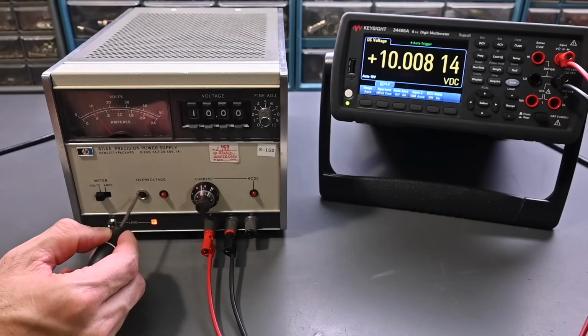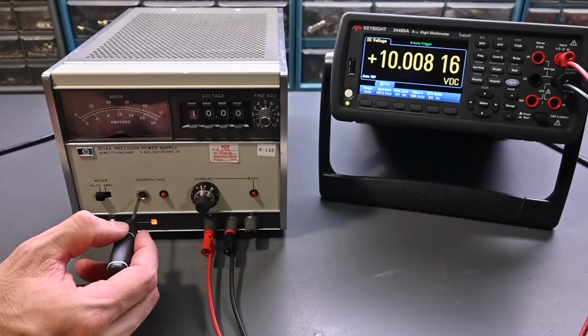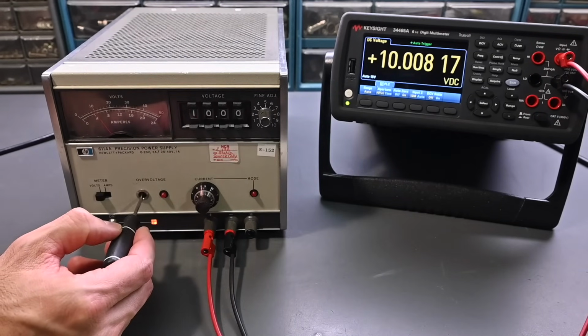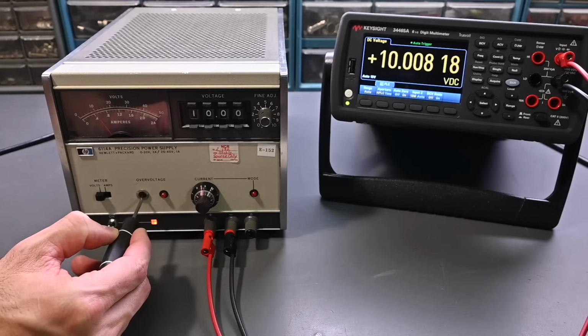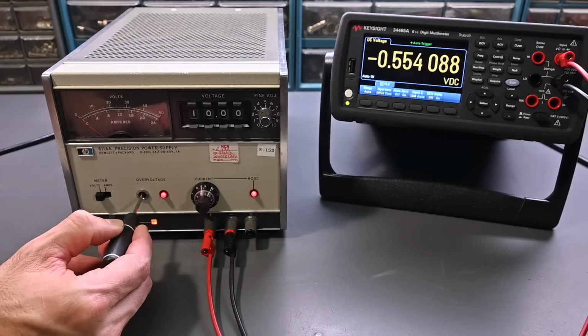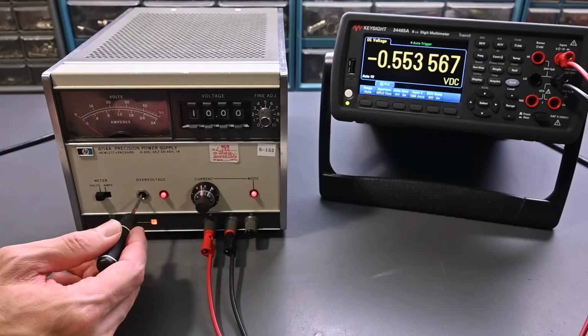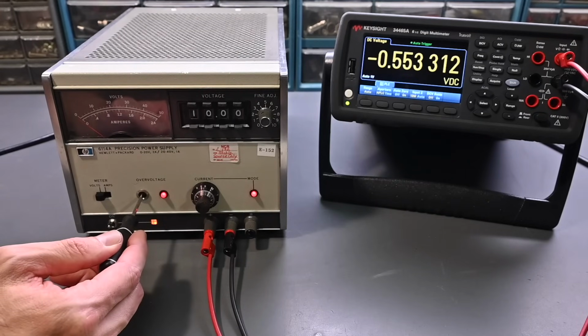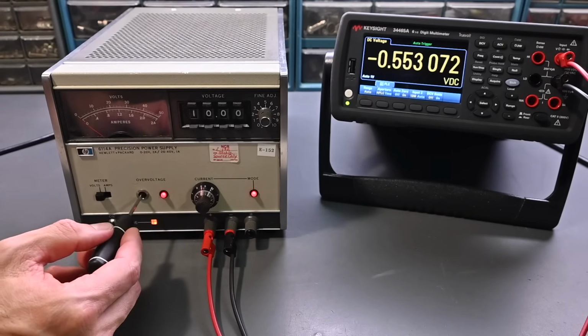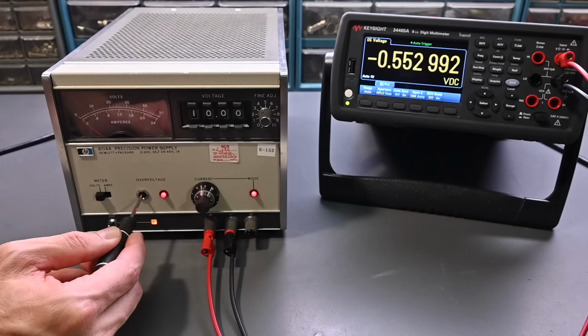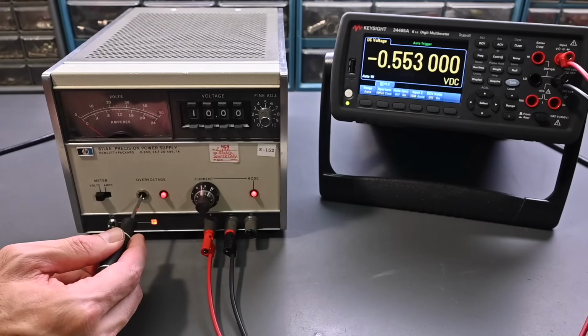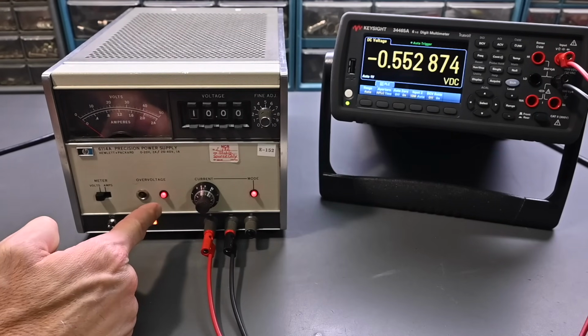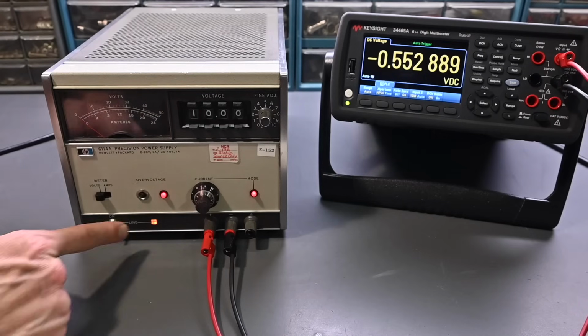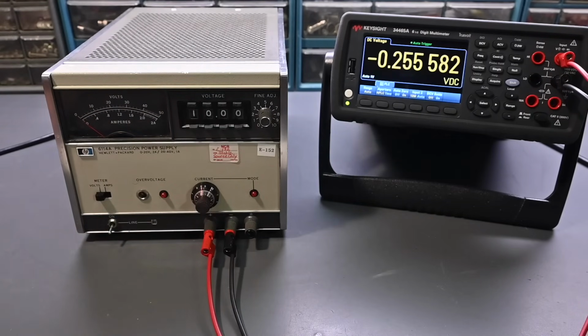Now the overvoltage adjustment in here, you just take a little screwdriver and you can reach in, and it's turned all the way to the maximum right now. So if I reach into the slot right there, I can't turn it, and you see it happened, it actually just went to overvoltage. But I can't turn it any further clockwise, so it's at its maximum, which should be above 40 volts. Basically just wiggling that a little bit, it didn't turn because it's already at its maximum rotation. It went into overvoltage, and it shuts the output off, and the power supply, everything shuts down. So the only way to reset that is to turn the power supply off.